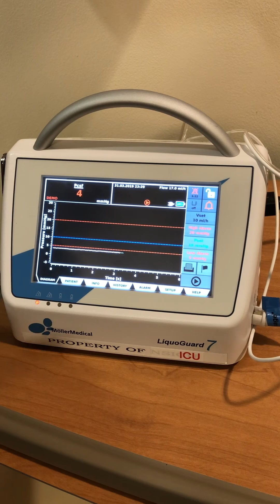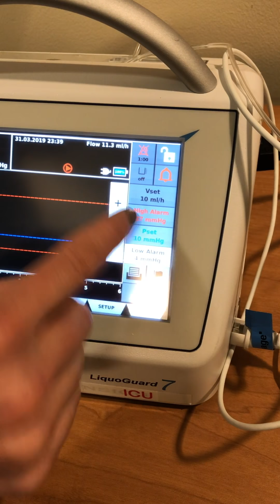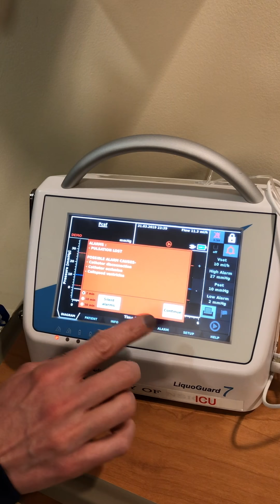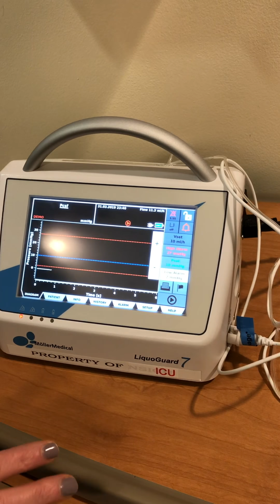You may get some alarms. The big alarms you'll hear is low pressure, no pulsation, or low flow alarms. So in that case, what the big things are, it's usually your catheter is kinked, it's become clogged or dislodged. So you also may need to adjust your high and low alarms right here, which you can adjust, we'll just say to 25, down to 4. You can go as low as 0, I believe. So you don't want it alarming all shift. You have to adjust them.